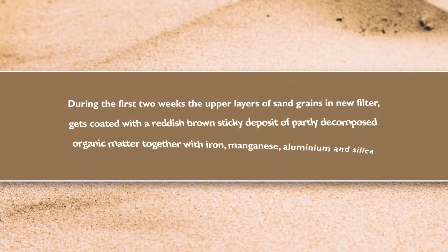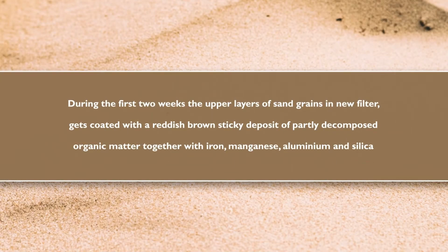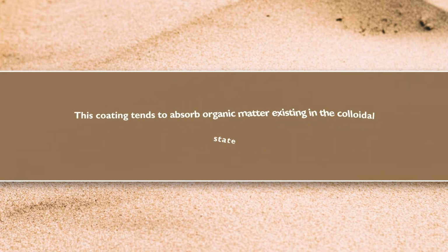During the first 2 weeks, the upper layer of the sand grains in a new filter gets coated with a reddish-brown sticky deposit of partially decomposed organic matter together with iron, manganese, aluminium and silica. This coating tends to absorb organic matter existing in the colloidal state.